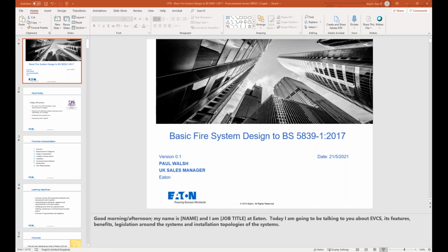You have got an EN54 Part 23 open class category, but again, that needs to be checked with the manufacturers, what they intend it for and specific applications. So it's maybe for an existing design that cannot meet precisely the EN54 Part 23 coverage, but the open class product needs to have its own coverage data well defined by the manufacturer to make sure that they've got an effective application.